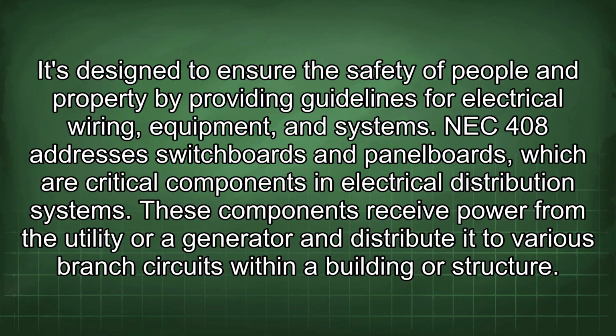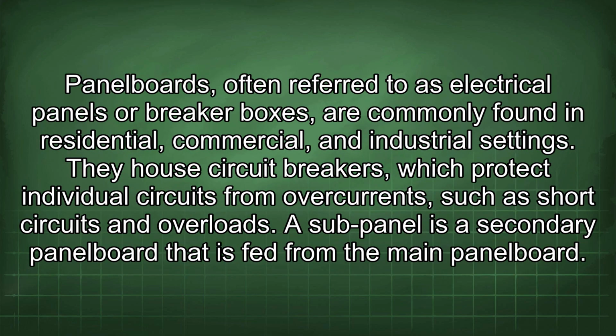NEC 408 addresses switchboards and panel boards, which are critical components in electrical distribution systems. These components receive power from the utility or a generator and distribute it to various branch circuits within a building or structure. Panel boards, often referred to as electrical panels or breaker boxes, are commonly found in residential, commercial, and industrial settings. They house circuit breakers, which protect individual circuits from overcurrents such as short circuits and overloads.